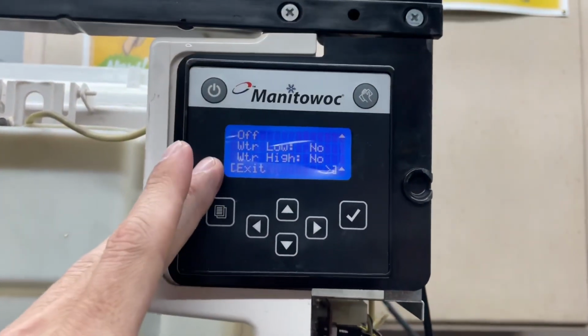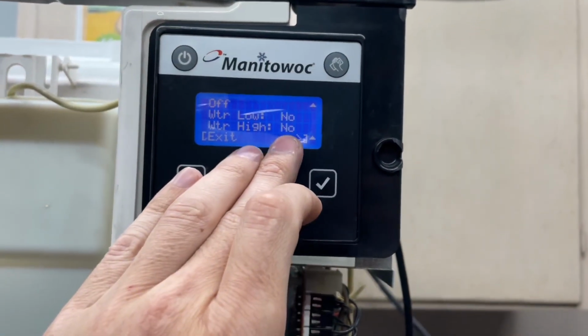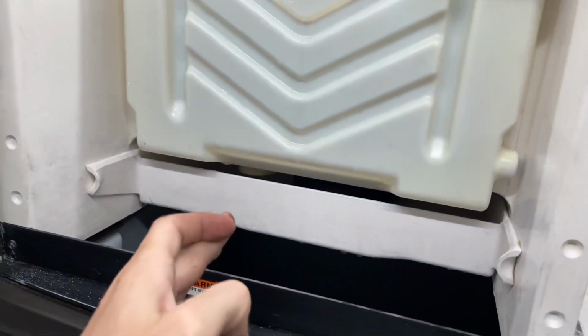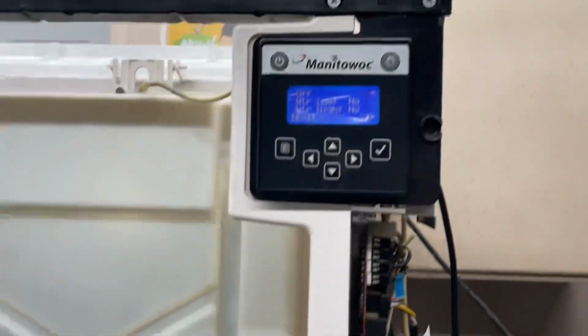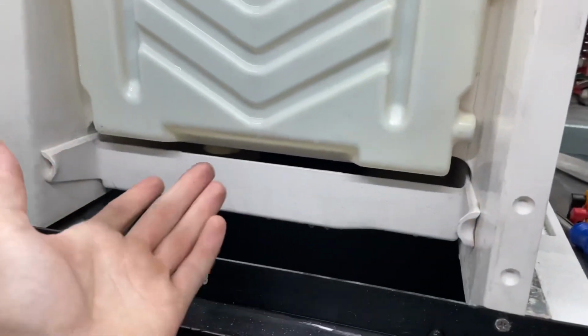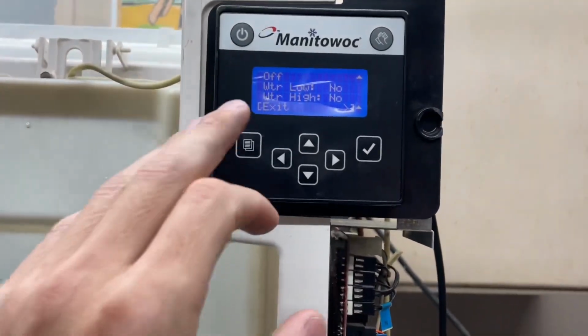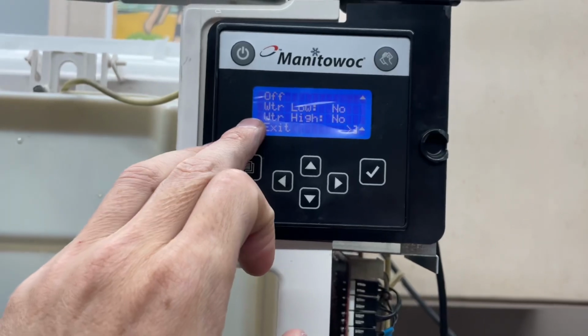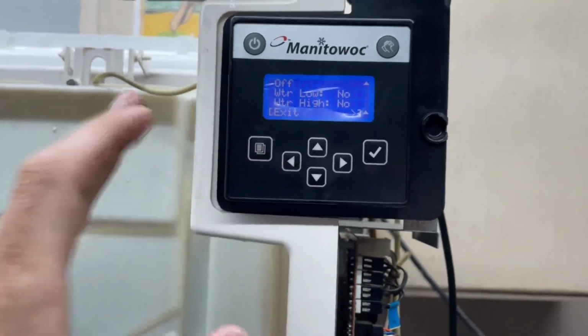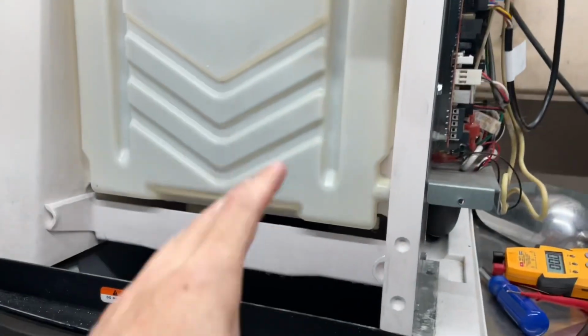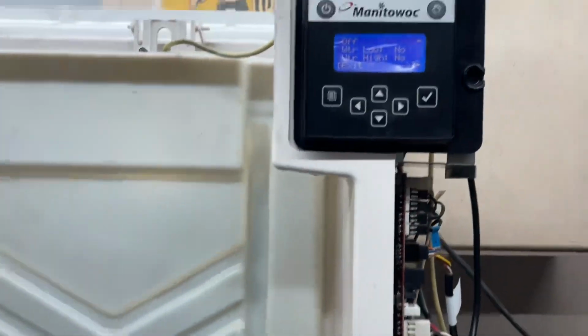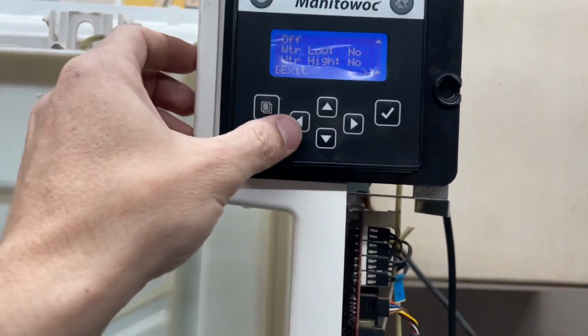But if you had run into an issue where they said yes and yes, but there was no water in the tray, then your machine's never gonna call for water because it's gonna think that it's already full of water when it's not. And that would lead you to believe that you have a bad water level probe. So in my opinion, step 1 is check your water level probe. Make sure that's working correctly.